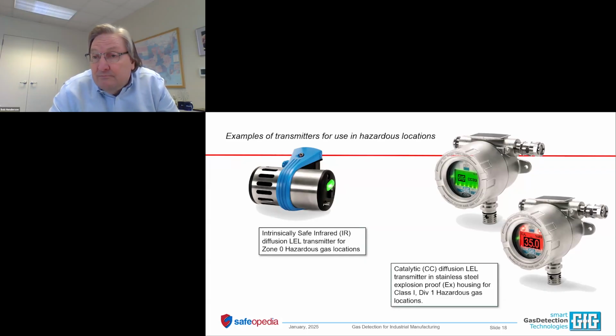So if you don't need that, don't spend money on it. But if you do have a hazardous location and you have that requirement, then that's your solution. Now, there are two protective methods that you can pick from with your transmitters. Manufacturers, as I mentioned before, have more than one product that they can steer towards depending on your needs. One protective method is to deal with the hazards by containing them in an explosion-proof junction box and conduit. Another approach is to design the product so there is no electrical energy that is around to be released under any circumstances.